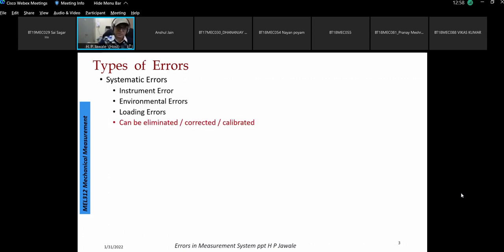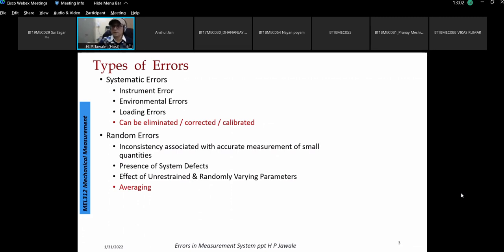We saw that systematic error is because of instrument error, environment, or loading error. The important part is it can be made known after having consistent readings or through the proper process. So we can have elimination, corrections, or calibration of the systematic error, whereas random error is one that can be found out by means of averaging.